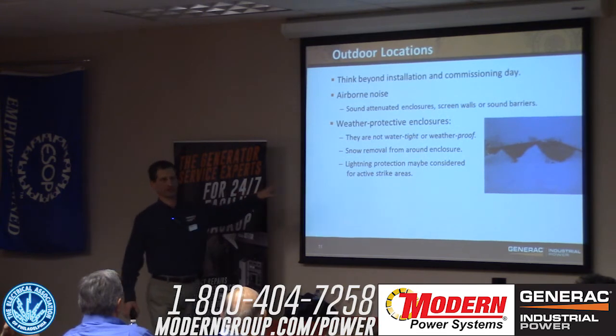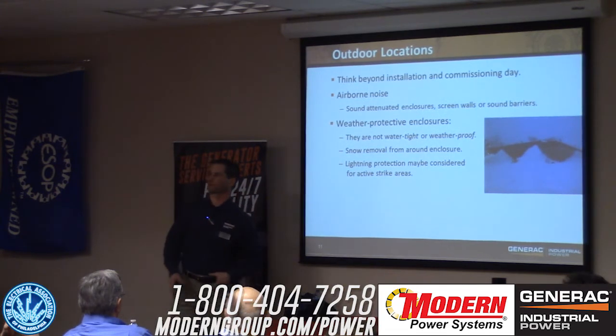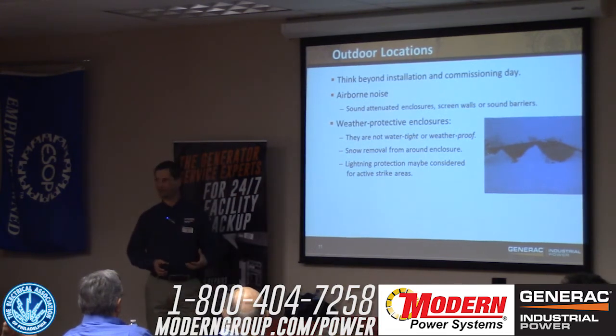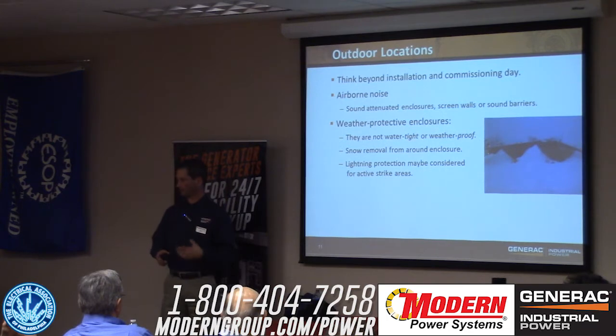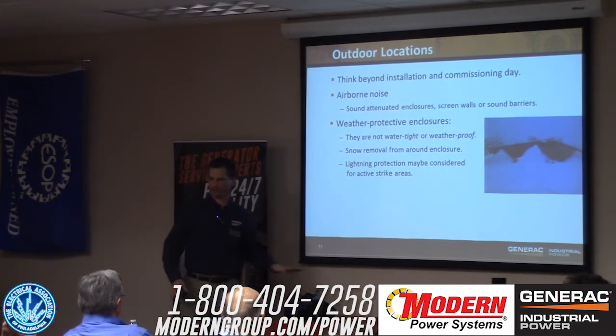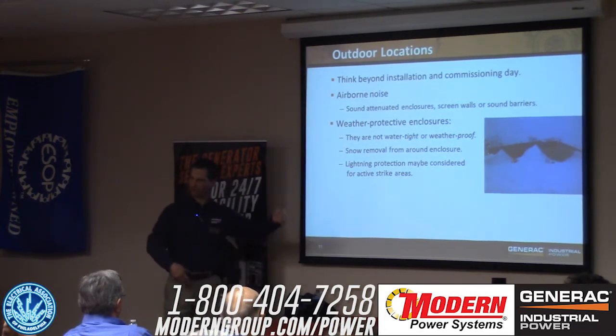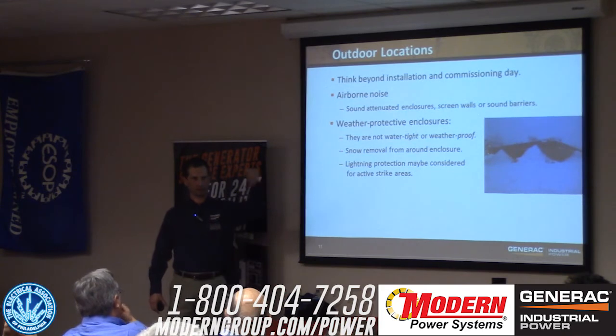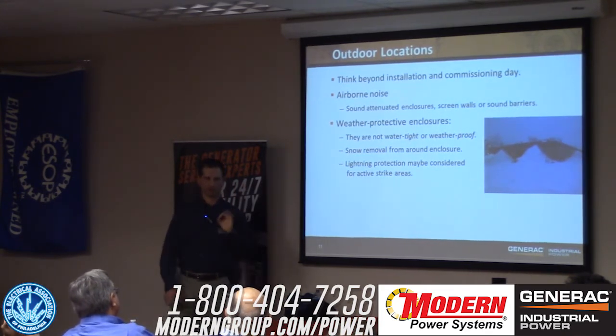If you're going to put the gen set on the roof, I don't have any pictures of them around here, but consider extending the lightning protection system to include the generator enclosure. If the building's got or is going to have a lightning protection system on it, it's super easy to just extend those conductors over the generator enclosure. They'll just kind of epoxy the air terminals onto the 4 corners of the gen set. The cables will run down the side of the enclosure and you're good to go.